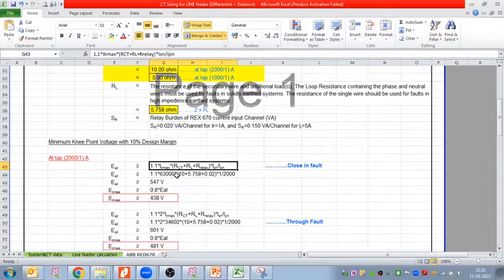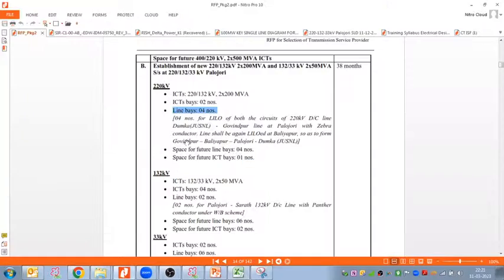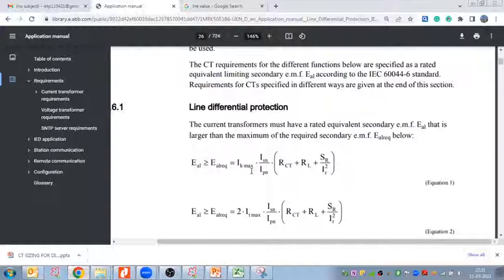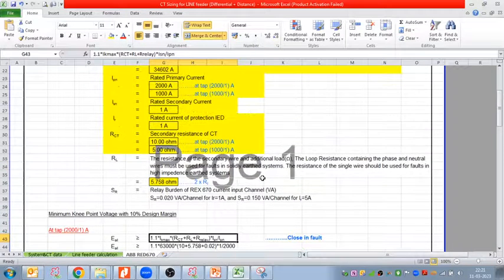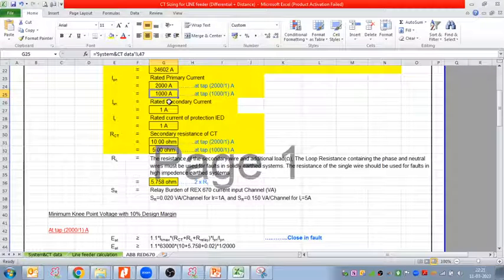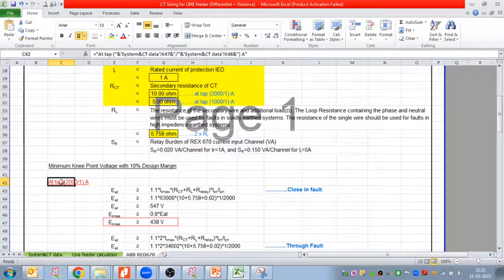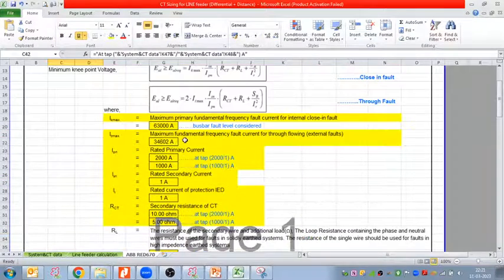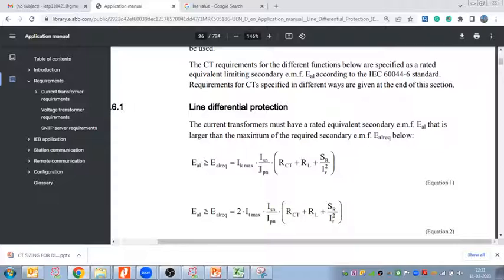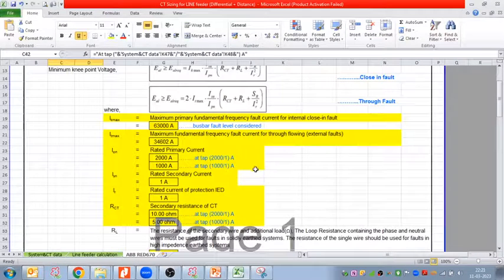So 1.1 into IK max into ISN divided by IPN. ISN is 1 divided by the primary current, and now we have two tappings, 1000 and 2000 for the CT. So we need to calculate the knee point voltage for both the tappings. Suppose I am taking the 2000 ampere tap. So at tap 2000 by 1 ampere, my CT primary current IPN would be 2000. So 1 divided by 2000, just that.